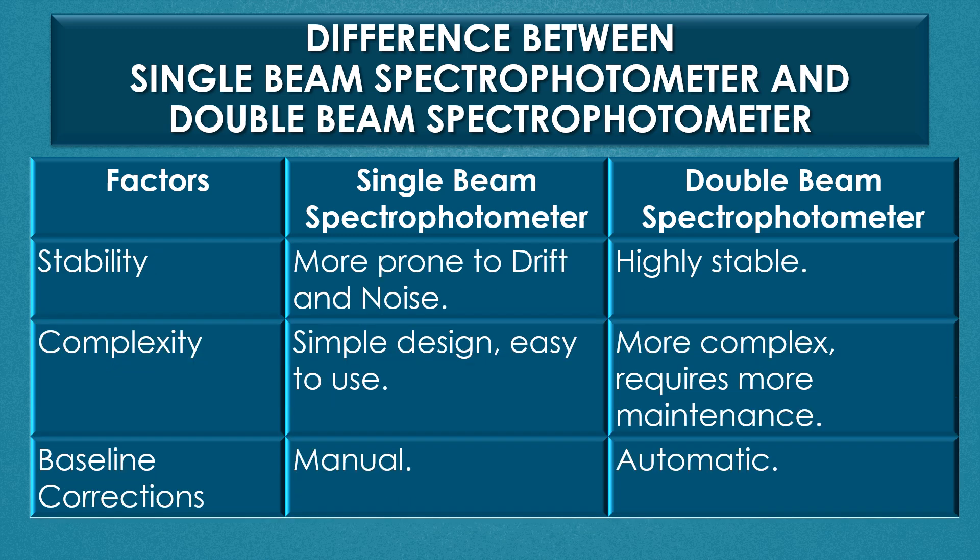Stability: a single beam spectrophotometer is more prone to drift and noise, and the double beam spectrophotometer is highly stable. Regarding complexity, a single beam spectrophotometer has a simple design and it is easy to use, but the double beam spectrophotometer is more complex and requires more maintenance.